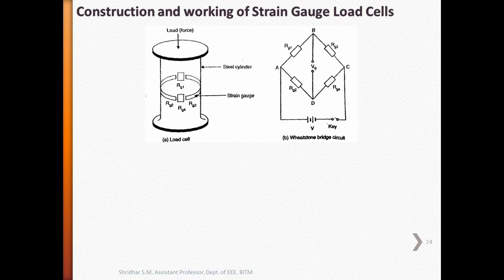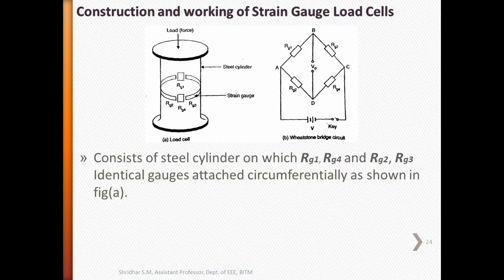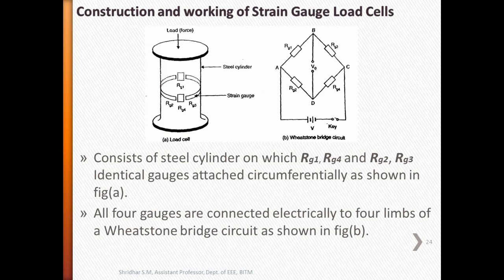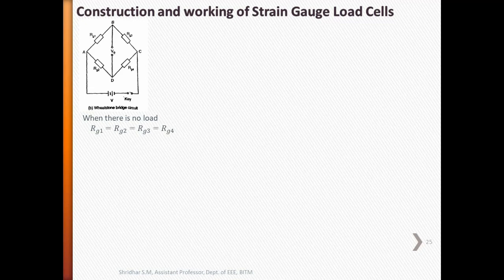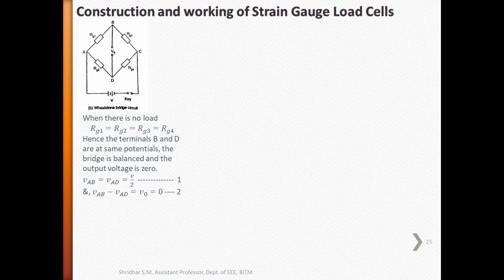Next, we'll discuss the construction and working of strain gauge load cells. A diagram shows a simple strain gauge load cell consists of steel cylinder on which four identical strain gauges are mounted, RG1 to RG4. All four gauges are connected electrically to four limbs of a Wheatstone bridge, which is shown in figure B. When there is no load on the cell, all four gauges have same resistance: RG1 = RG2 = RG3 = RG4. Obviously, the terminals B and D are at same potential. The bridge is balanced and the output voltage is 0, which can be given by equations 1 and 2.